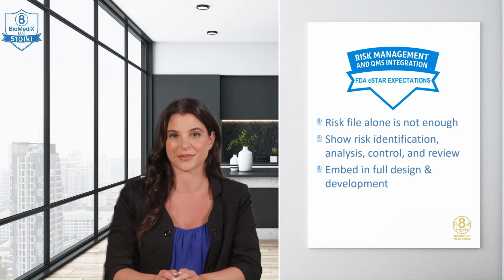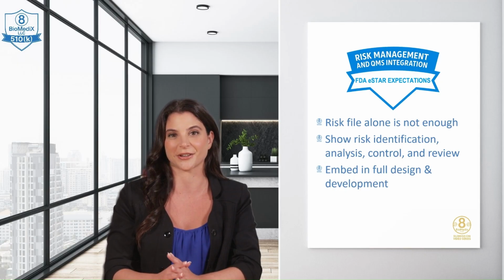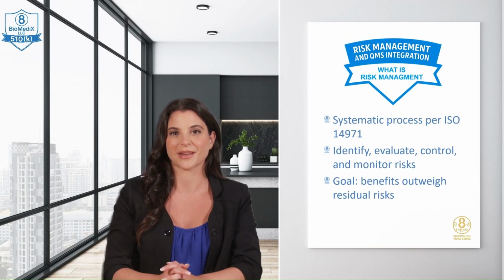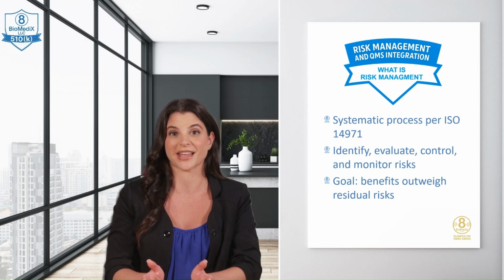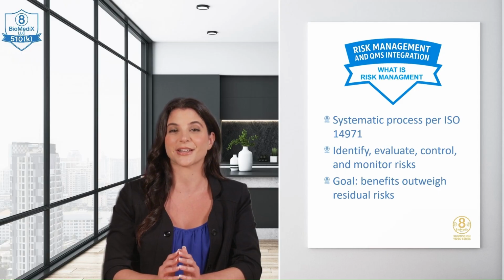It's not enough to simply have a risk file. Your eSTAR submission must demonstrate how risk has been identified, analyzed, controlled, and reviewed throughout your device's design and development. What is risk management? At its core, risk management in medical devices is a systematic process for identifying, analyzing, evaluating, controlling, and monitoring risks associated with the use of a medical device.